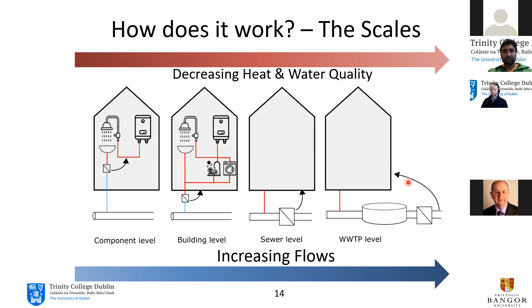If we talk about the wastewater treatment plant, this acts as the hub where a high volume of wastewater comes from different locations: residential, commercial, and industrial sectors. It arrives directly at a hub tank with high volume content, but lower temperature compared to the component, building, and sewer levels. However, the high volume flow rate is an advantage, allowing maximum heat recovery, which can be used for district heating.